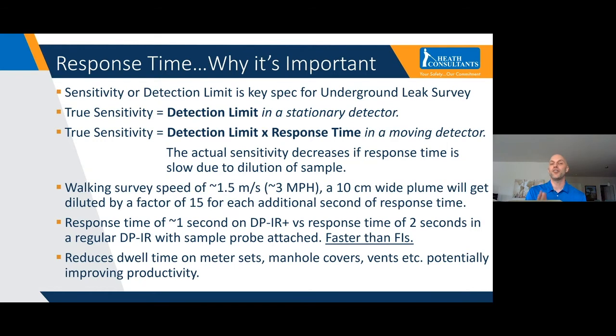That may not mean much to you on its own, but the bottom line is it rapidly increases the response time. This slide talks about why response time is actually important when comparing an instrument's sensitivity. If an instrument says it has a sensitivity of 1, 2, or 10 parts per million, and the response time is slower, that could actually lead to negative effects on the sensitivity side. This primarily affects smaller leaks.